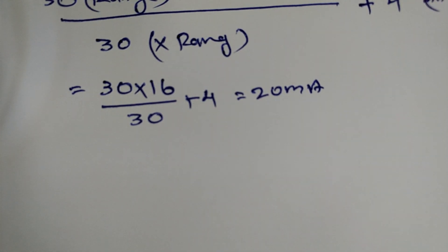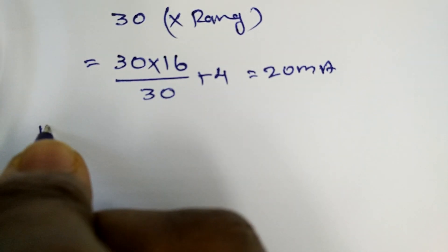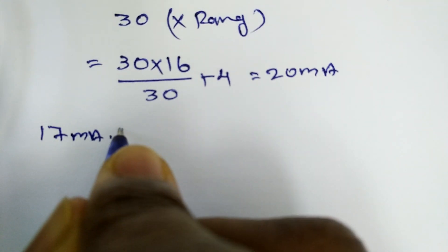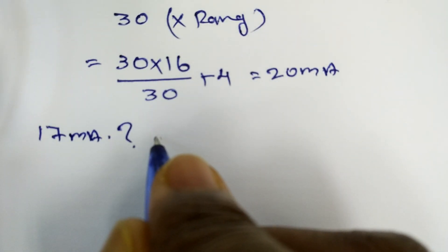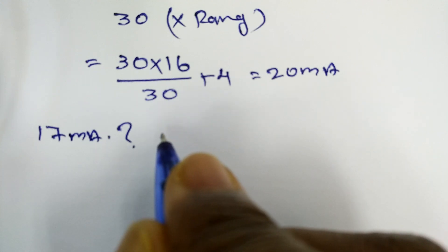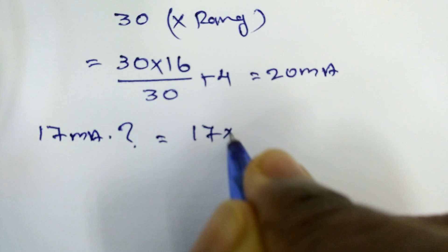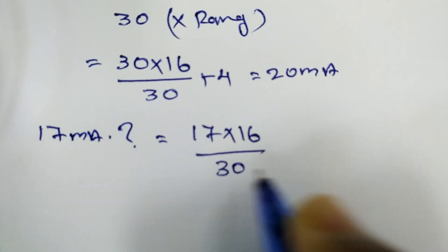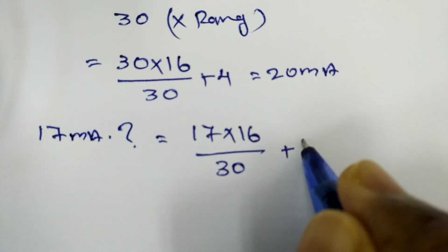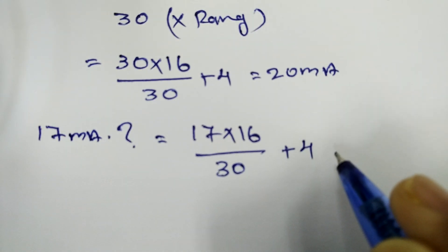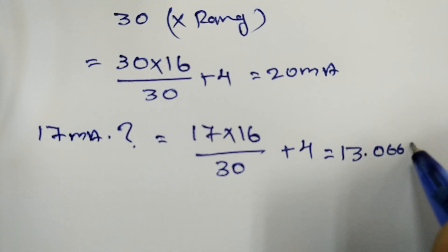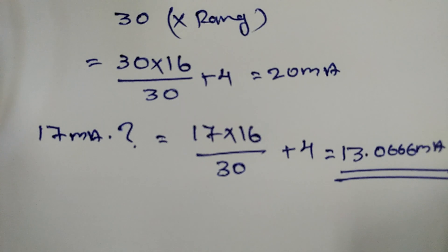Suppose we have a client's requirement of 17 mA input value. We will substitute the value of 17 into the equation: 17 multiplied by 16, divided by the 30 range, plus 4. This calculates to 13.0666 mA.